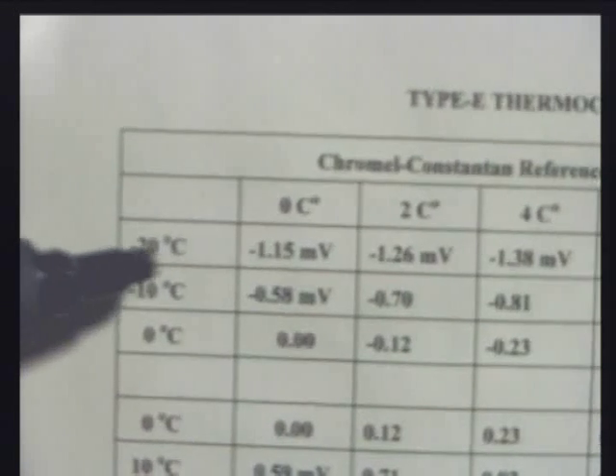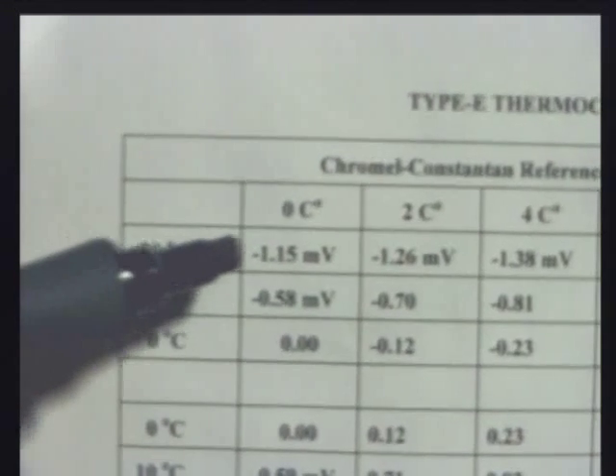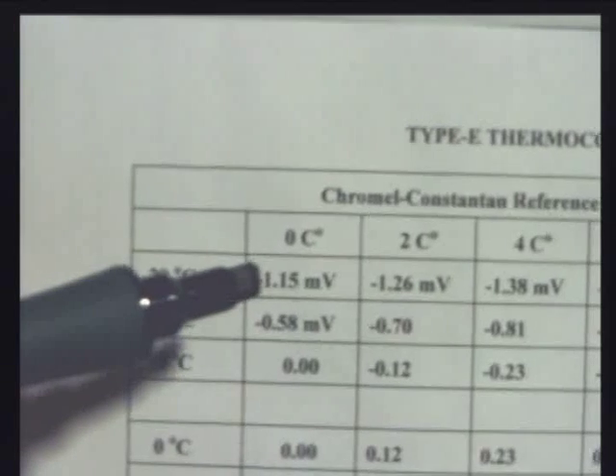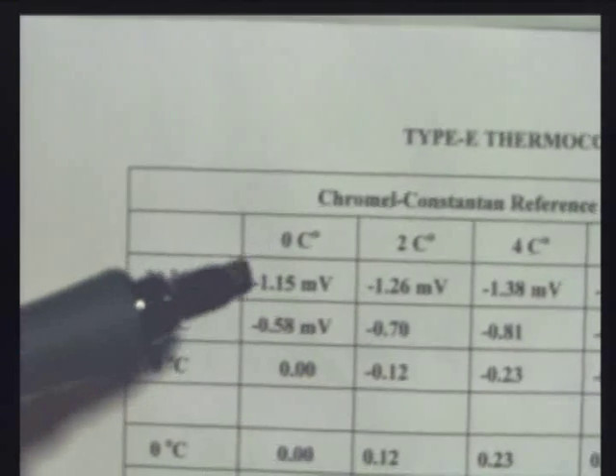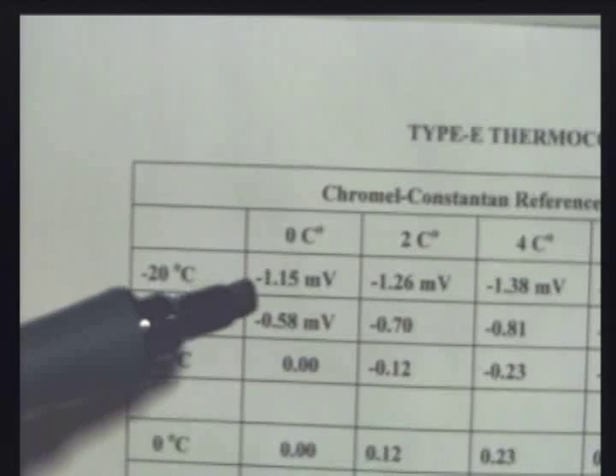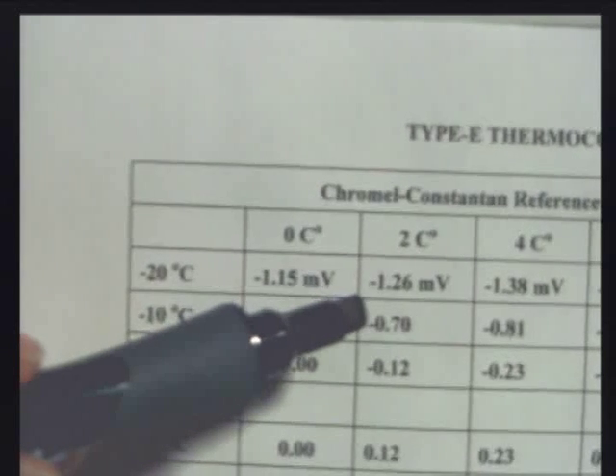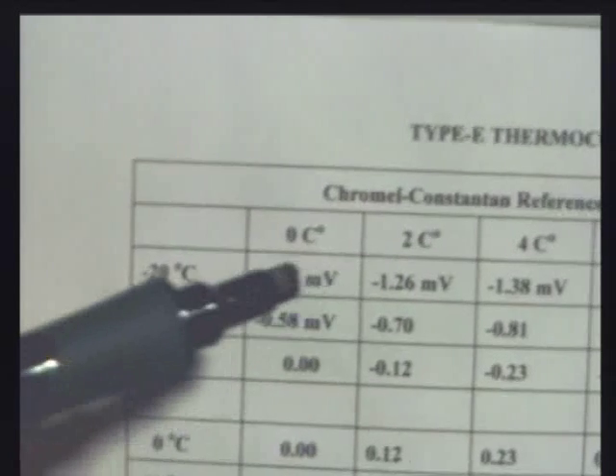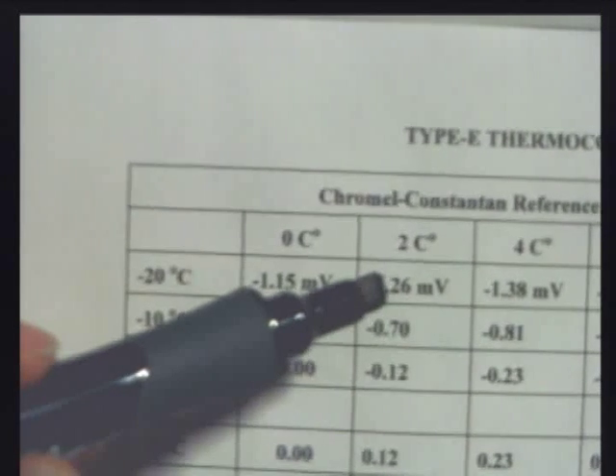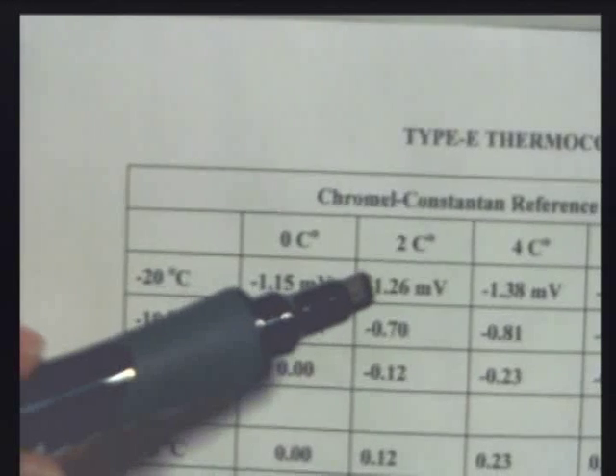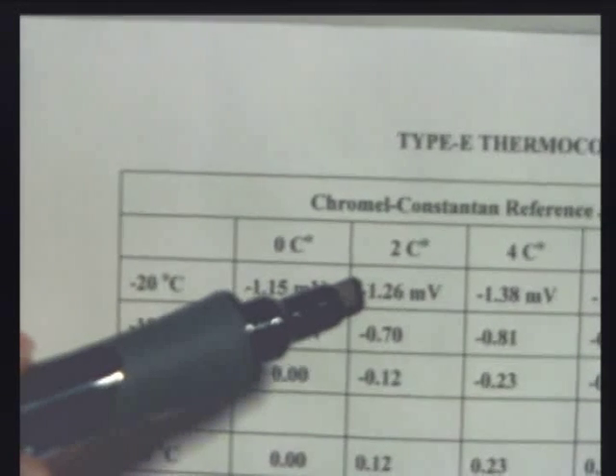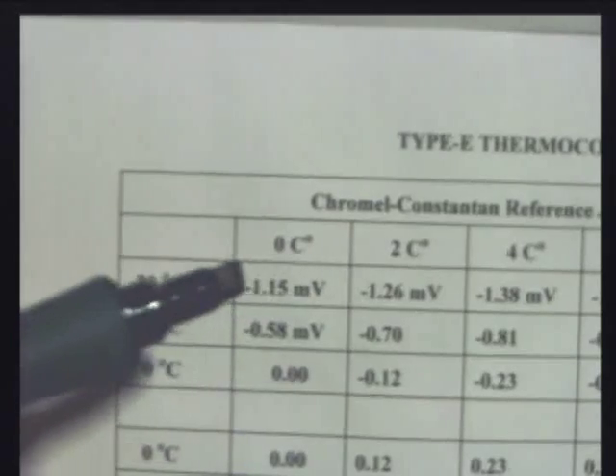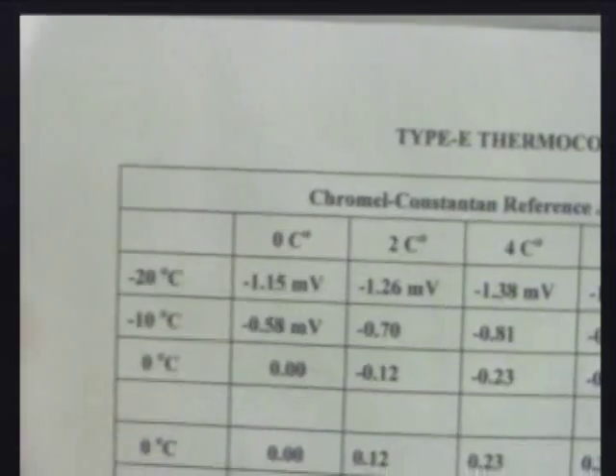So there's minus 20. There's 0. That's minus 20, that's minus 22. It's between minus 20, which is minus 1.15 millivolts, and minus 22, which is minus 1.26. It's almost smack in between. So there's minus 20, there's minus 22. My temperature difference must be minus 21, halfway between.